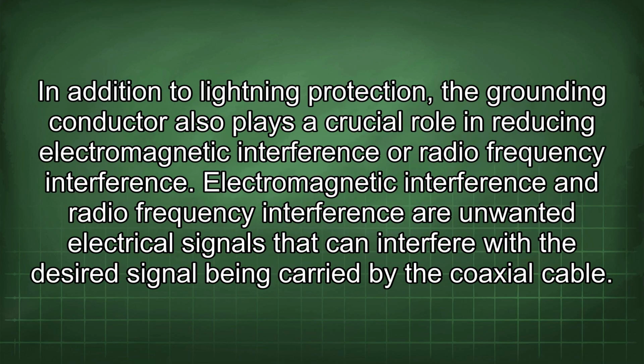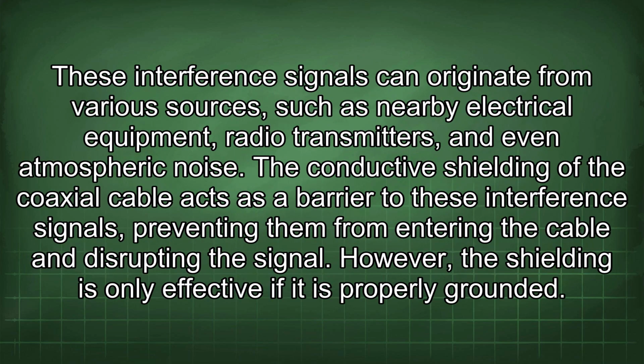In addition to lightning protection, the grounding conductor also plays a crucial role in reducing electromagnetic interference or radio frequency interference. Electromagnetic interference and radio frequency interference are unwanted electrical signals that can interfere with the desired signal being carried by the coaxial cable. These interference signals can originate from various sources, such as nearby electrical equipment, radio transmitters, and even atmospheric noise. The conductive shielding of the coaxial cable acts as a barrier to these interference signals, preventing them from entering the cable and disrupting the signal.